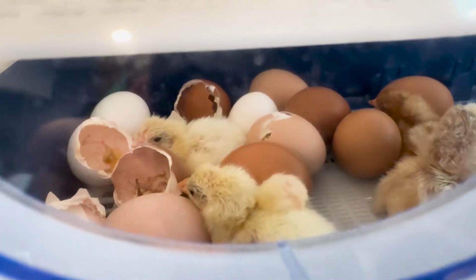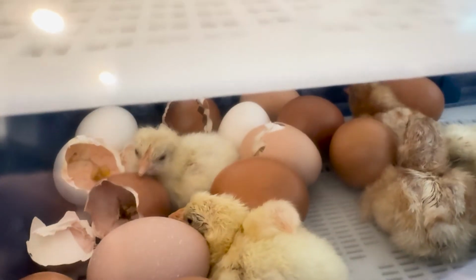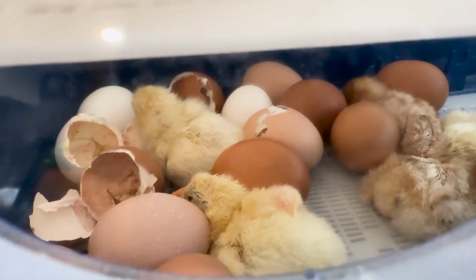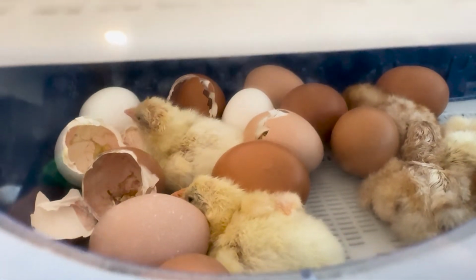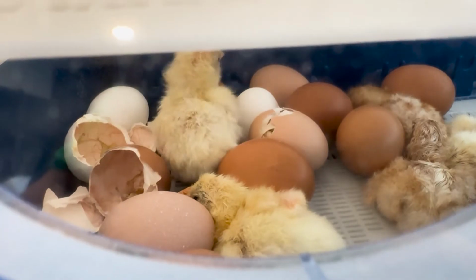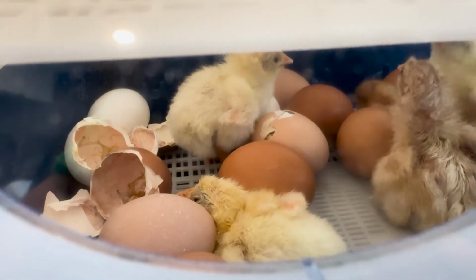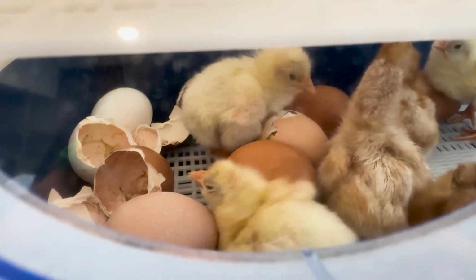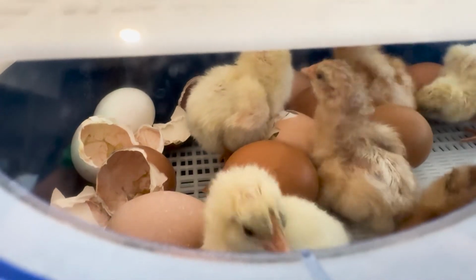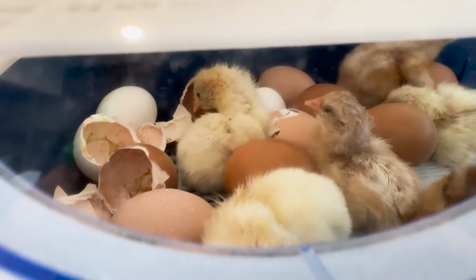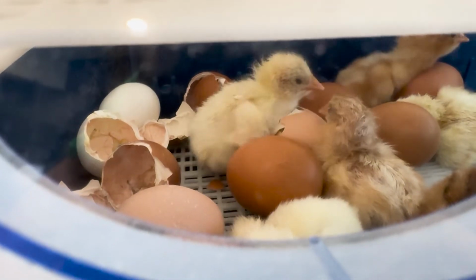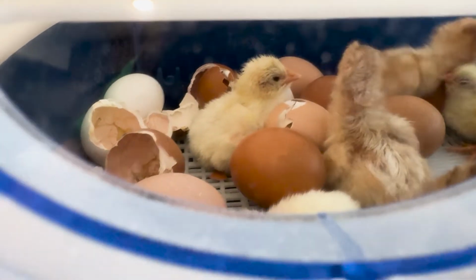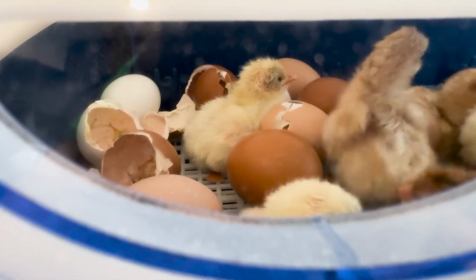Now, the next important factor is incorrect calibration of the equipment, or potentially malfunction. Especially if your incubator is equipped with a thermometer and a hygrometer, you want to make sure they are calibrated correctly and have the right reading so they don't over-adjust or under-adjust the temperature or the humidity. That can cause issues, and ideally you want to have them calibrated every so often, or at least double check with an external thermometer before you use the incubator, to make sure the levels it shows on the display are actually what's happening on the inside.